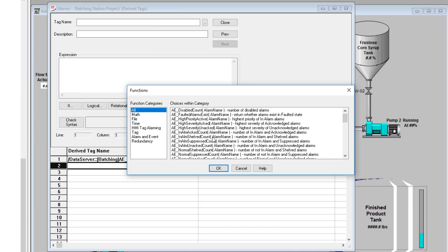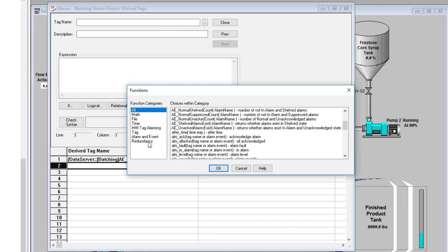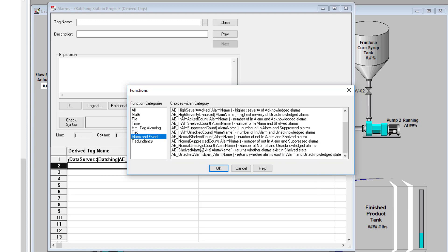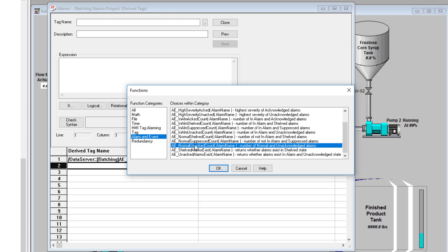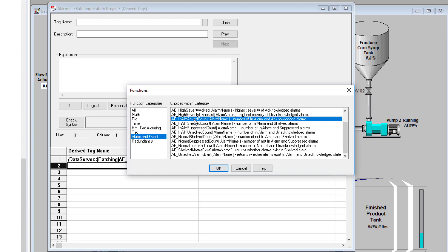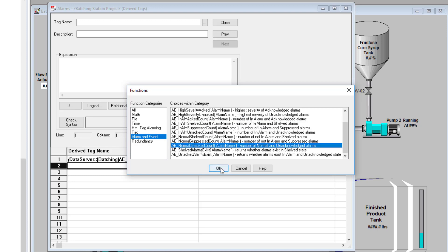We're going to do another function — let's do a count. A cool widely popular one would be a count of unacknowledged alarms. You've got unacknowledged, you've got shelved — you can do a count of shelved alarms if you ever wanted to know how many shelved alarms you have. Or you can do a count of normal unacknowledged count, which is going to come back and give you the count of unacknowledged alarms.